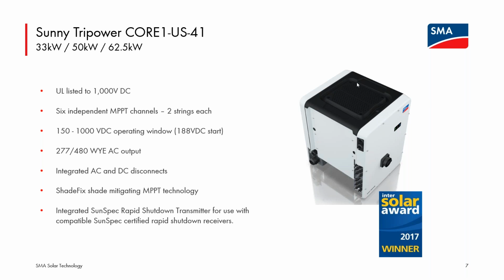In this picture, it's not as clear as other images we have later in the presentation. The black top cover of the inverter, there are actually holes in this center, and this may be where the product name came from. The center core of the inverter is actually a thermal chimney. So there are heat sink fins that protrude into that center area, and there's an airflow path up the center of the inverter. And in fact, there is a fan tray located at the bottom of that airflow path, and those fans are temperature controlled. So when the inverter's internal temperature hits a certain level, those fans will come on and begin to force air up this thermal chimney. So you have natural convection backed by forced convection for the cooling.